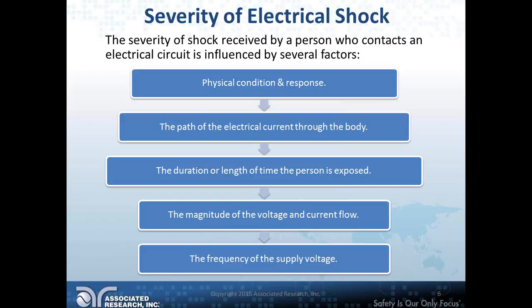Frequency makes a big difference. There's a weird range of frequency - off the top of my head, I believe it's around 40 to 120 hertz - where it really reacts badly with your heart muscle. The way your heart beats and electrical impulses go from your brain to your heart, that frequency range really interrupts that. That's what happens when you get hit by something like line voltage, which in the United States is 60 hertz - a very disruptive pattern to your body. You can get hit by that and go into defib, and that's going to cause you problems. So these are things to consider when looking at risk analysis for an electrical shock hazard on a station or setup.